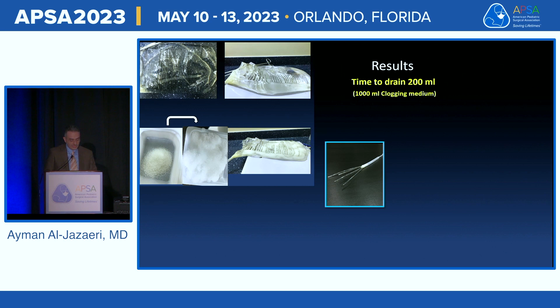We compared 3 types of catheter: the multipod catheter, a size-matched closed-tip catheter, and an open-tip catheter. You can see the results here. The white boxes represent placing the catheter in non-clogging medium of water. They all drain the first 200 ml within less than a minute. However, when we place the catheter in a clogging medium, the open-tip catheter stopped draining after 95 ml. The closed-tip catheter drained the first 200 ml within 9.5 minutes. And our catheter drained the first 200 ml within 1.5 minutes.